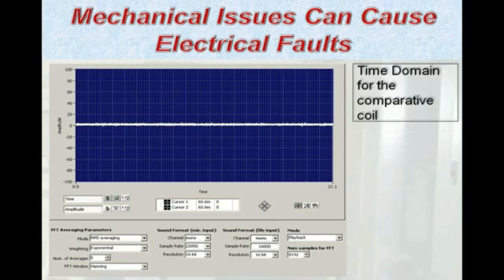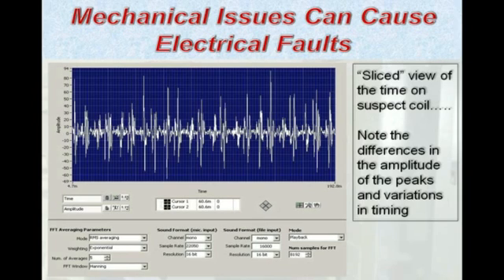By slicing up or magnifying the view of the suspect coil, you can see even clearer the differences in the amplitudes on these peaks, as well as some variation in the timing. In other words, the spacing between where these excursions or deviations take place. That's important when we talk about the timing of an electrical sine wave, because everything is very predictable on 50 and 60 hertz systems, and when we begin to have faults, the timing of those excursions can be affected, which is what the time domain tool is very good at illustrating.